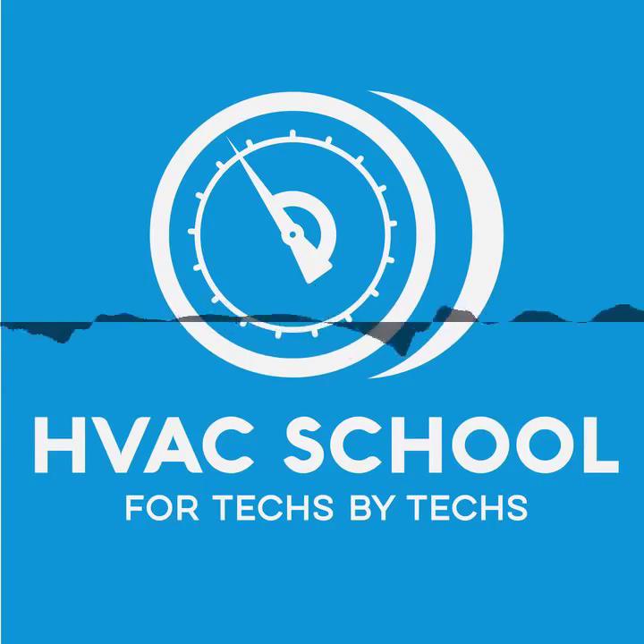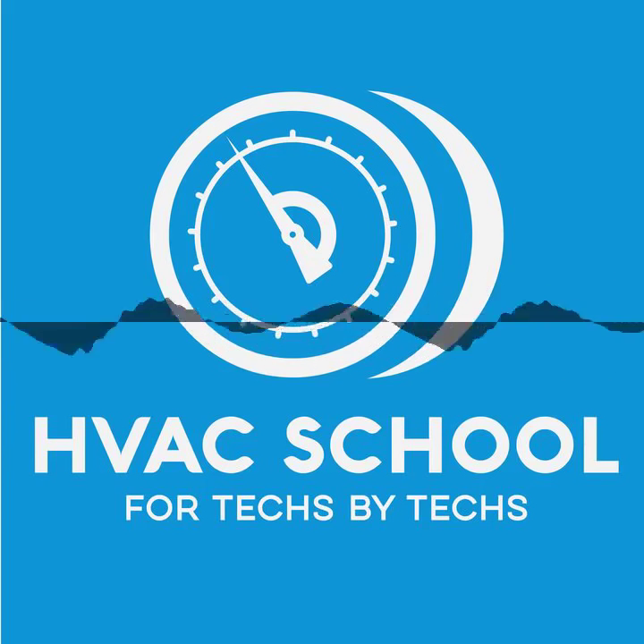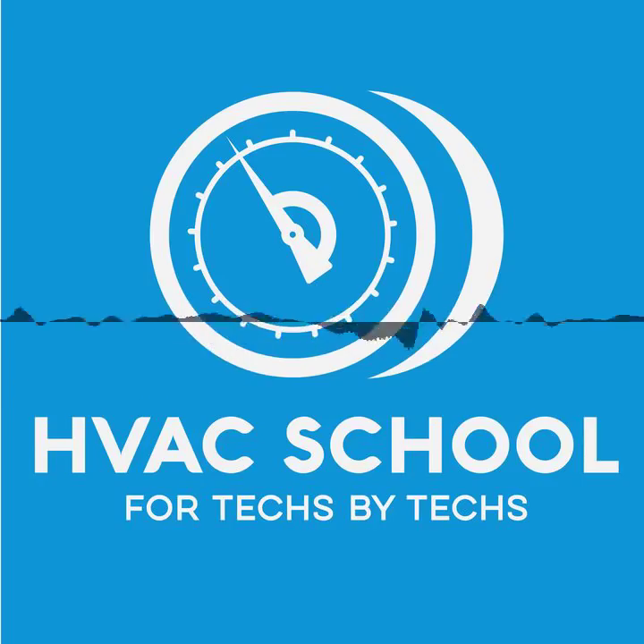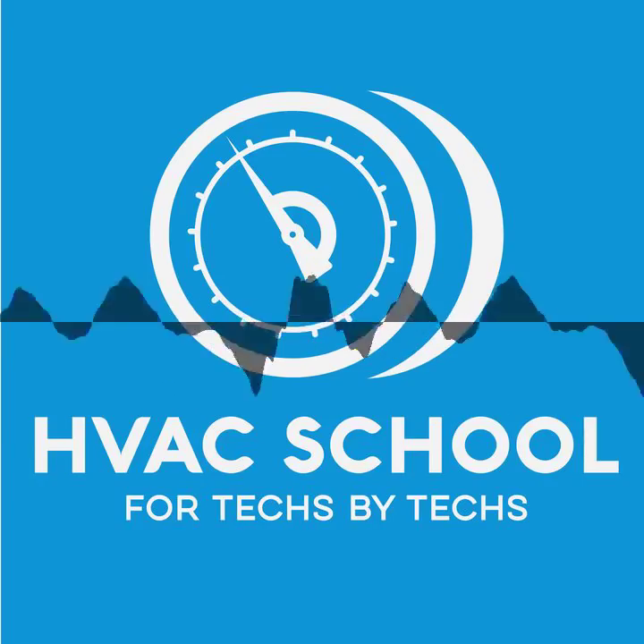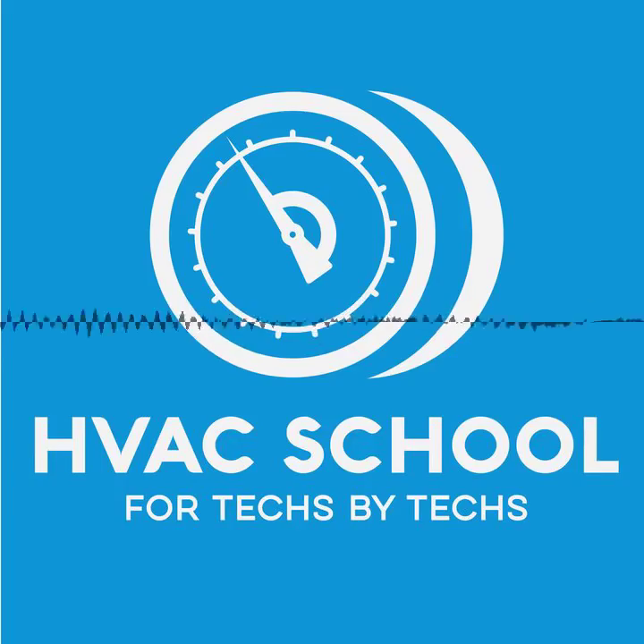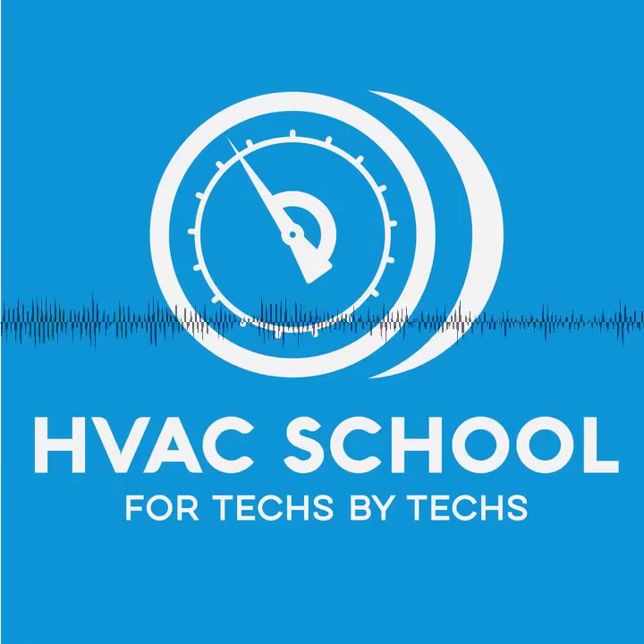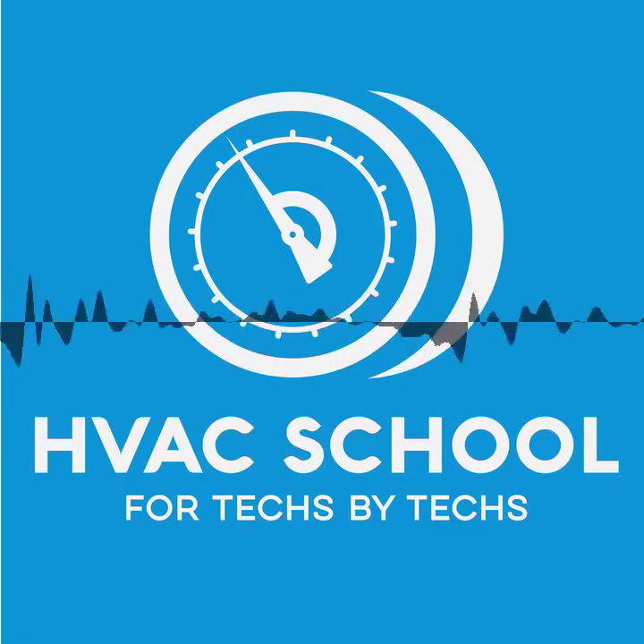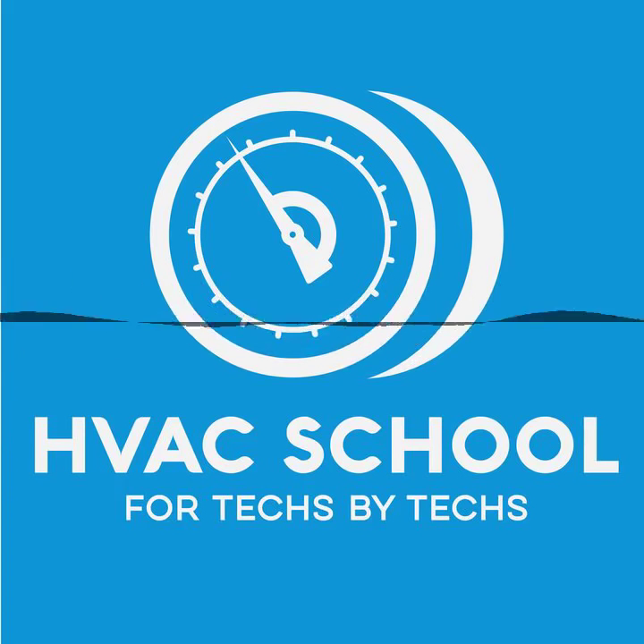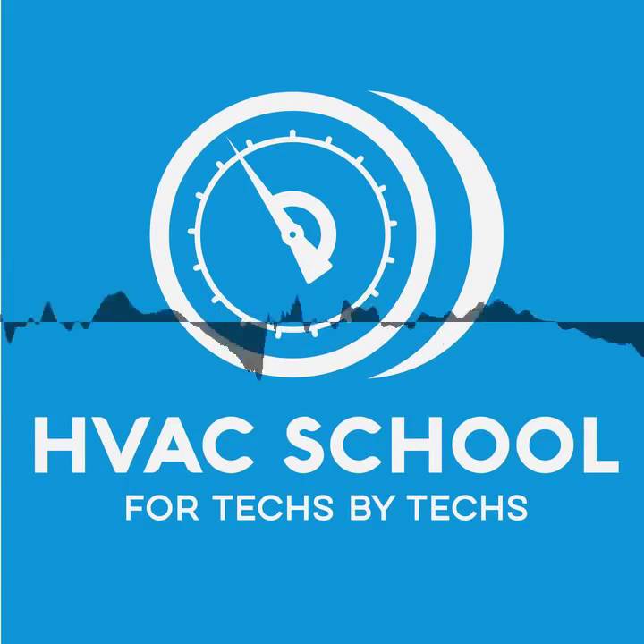That's basically it for this episode. I just wanted to give you a quick introduction to delta T. Don't use just a static measurement. Make sure you put your probes in the right places, in places where the air has a chance to mix and not in line of sight to cold surfaces. Use good quality probes. Don't use cheap little ones; I see some people still using the old dial probes, and it's going to be tough to get an accurate measurement with that. I talk all the time about how much I like the Testo 605i. That's sort of my tool of choice for this purpose, not just for delta T, but to do delivered capacity and a lot of other things you can do with those tools. So that's my tool of choice.